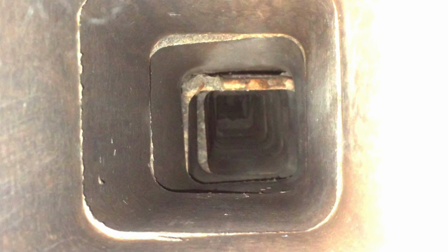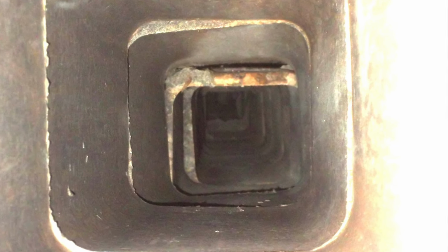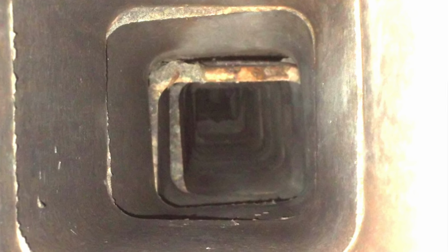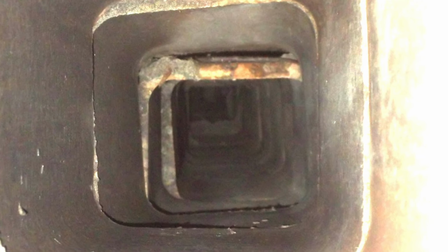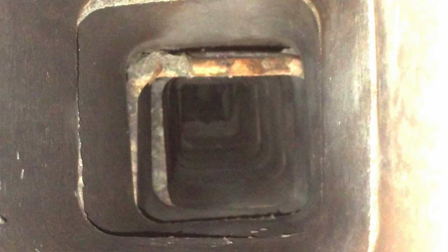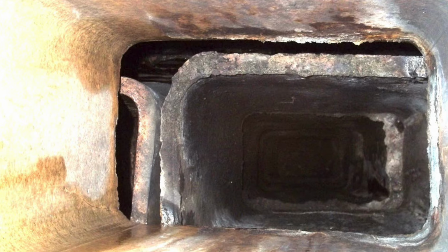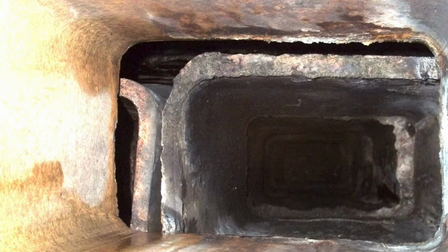Another serious consequence involves buckling. When both the bottom and top of the flue liner are restrained, bottom fixed by the smoke chamber, top fixed by the crown, the liner behaves like a column under compressive load. As the internal stresses build, the liner may not fully expand upward, so it begins to deflect sideways. This buckling effect may be extremely small, sometimes only a millimeter of lateral movement per heating cycle, but over years of operation, these millimeters accumulate into centimeters.